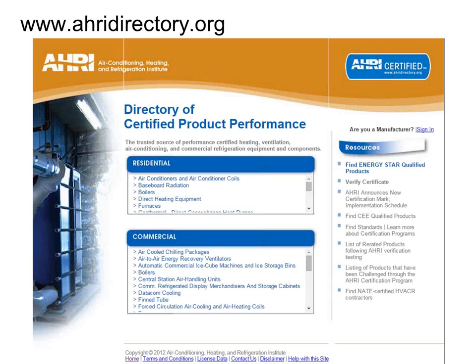But you can look at just about anything's capacity and efficiency by brand, by model number type of thing. So there's a residential category and commercial category. Just note that residential and commercial is the way they choose to list the products. It doesn't mean you can't use one and the other. So everybody knows we put small 3-ton DX split systems in a commercial building before. And everybody's probably heard of a job where we put a chiller in a house, right? That stuff happens all the time. So just kind of keep that in mind when you're looking at these lists.